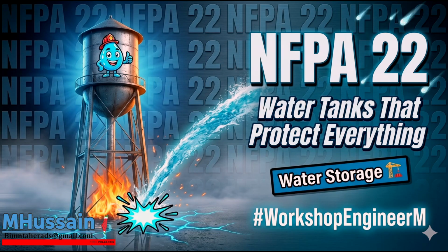Let's analyze those dimensions, because an engineer might look at a 4-foot steel plate inside a tank and think, well, that's overkill. Why mandate 48 inches wide, and why exactly 6 inches off the floor? It is about forcefully manipulating the fluid velocity vectors. By placing a massive flat barrier directly above the suction pipe, you physically block the vertical air funnel from reaching the pipe. You force the water to change direction. Exactly. The pump must now draw water horizontally from the outer edges of the plate, parallel to the tank floor, rather than vertically from the surface. This horizontal shear cuts off the rotational energy required to sustain a vortex.